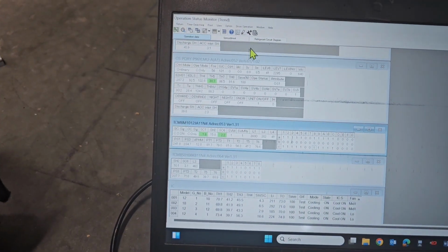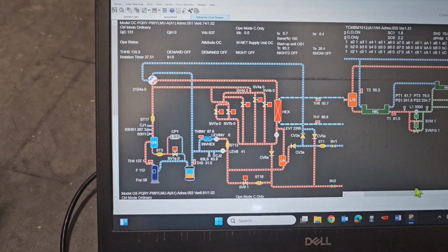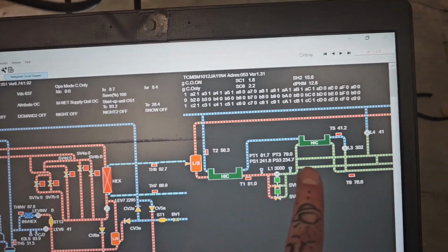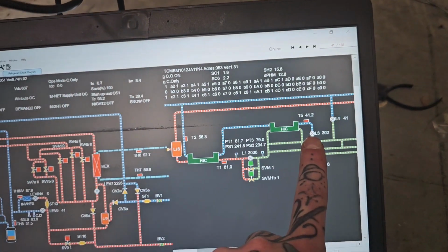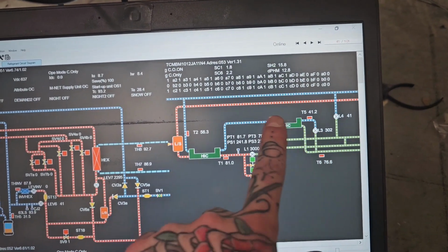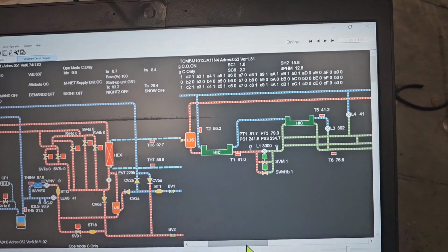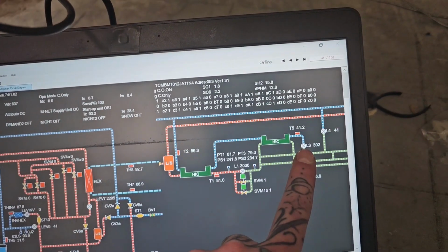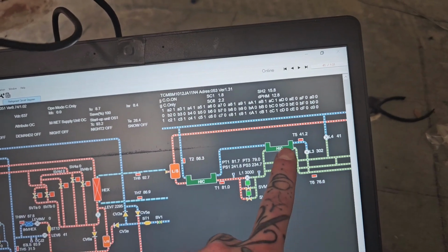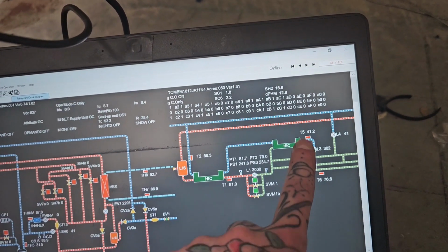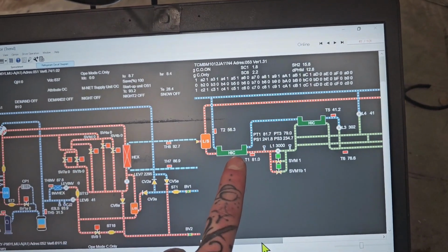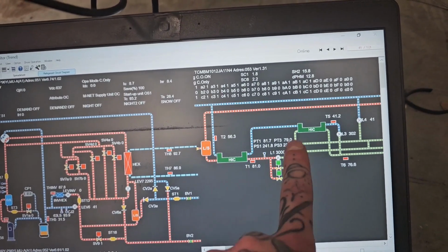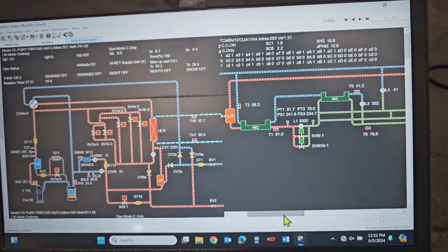Now, regarding that SH2, that is what is controlling our subcooling. Okay. So that SH2 controls this valve, and it says after our 2 subcoolers we want to see 4 degrees of superheat. If superheat is higher than 4, we're going to open up this valve, allowing more flash gas, more refrigerant in to then hit our subcoolers to cool down our high pressure line and condense that liquid and subcool it as much as possible.